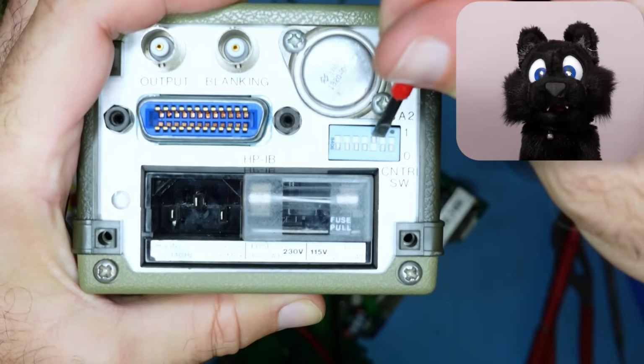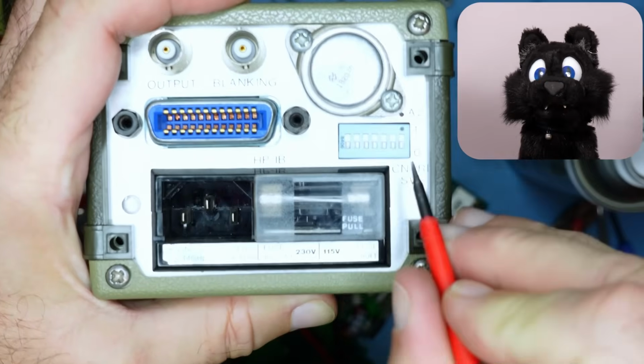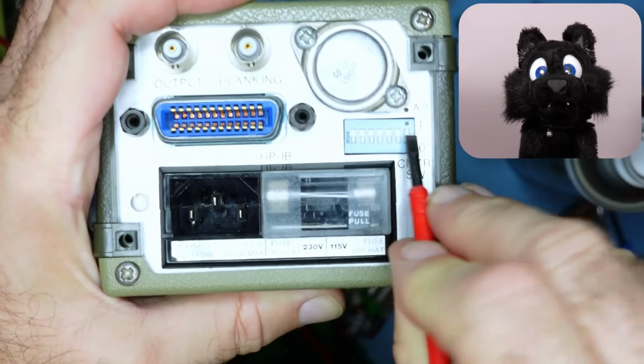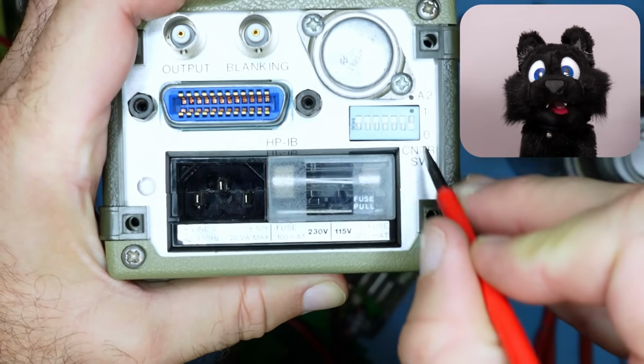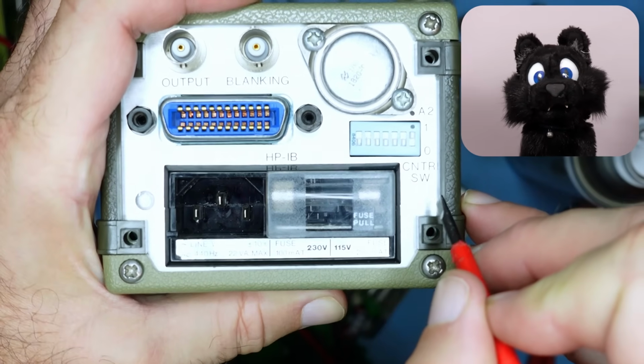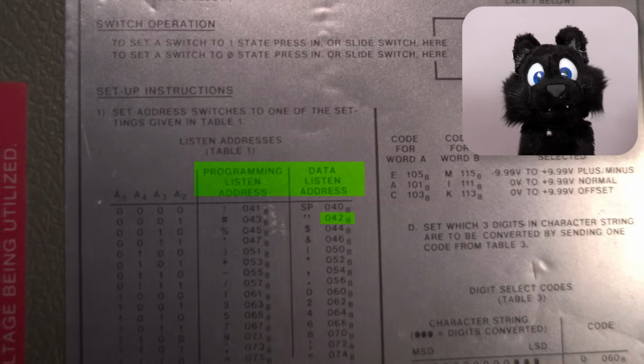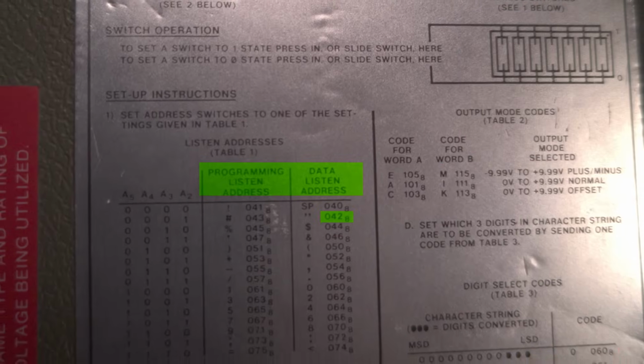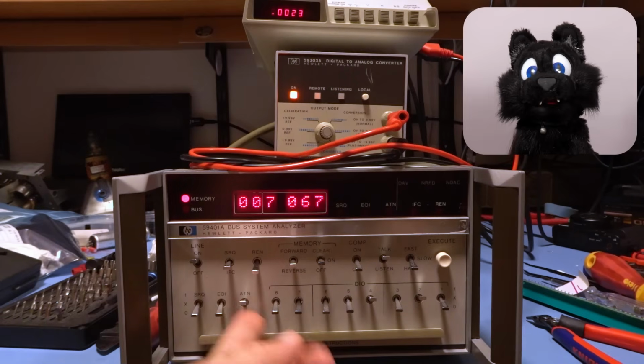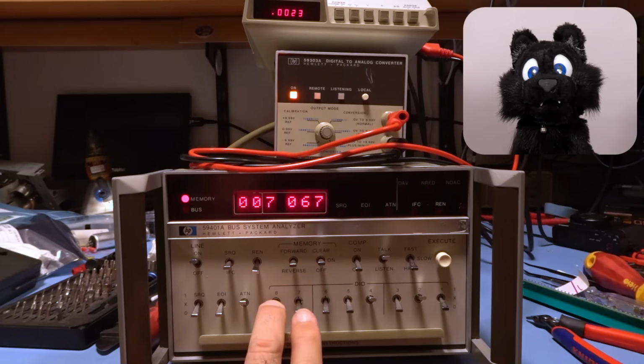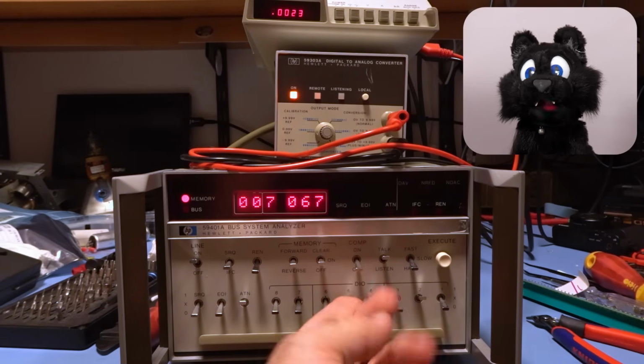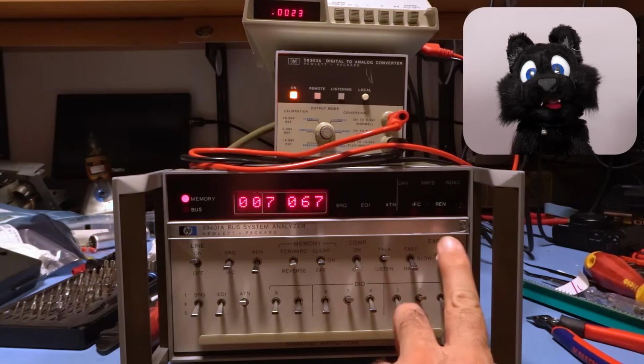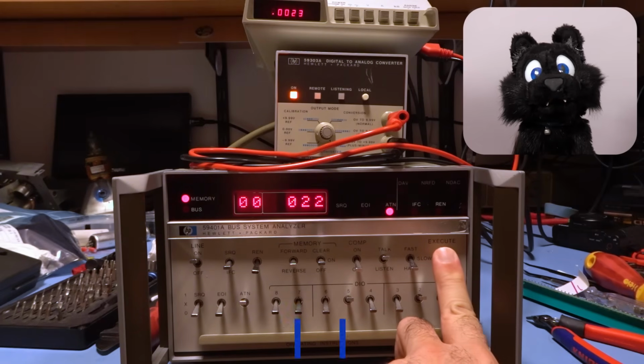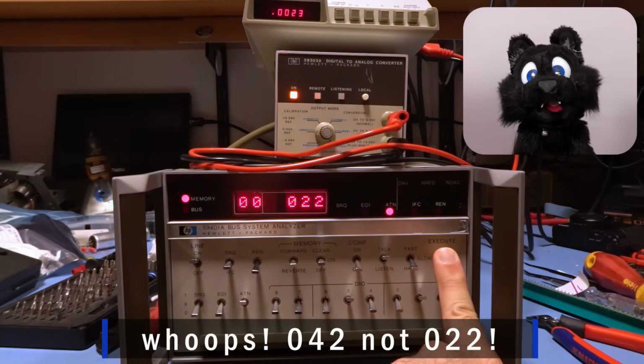Let's try the same thing with addressed mode. I'll set the DA converter to address 2. This automatically will listen to address 2 for data and 3 for the mode selection commands. The program in this case needs to read set listen address 2, send data string, and at the end, don't forget to unlisten. I'm sending 6.55 volts this time.